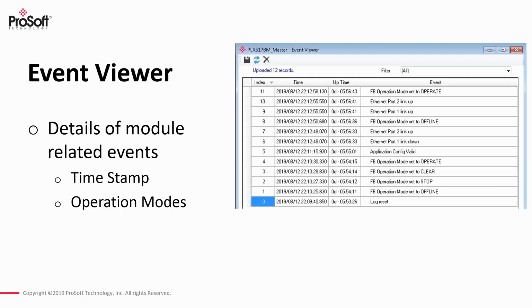And so say, for instance, you get an issue that occurs at 10 o'clock at night. When the maintenance crew comes in the next day, or they get things back up and running, somebody can go back through this event log, and it's going to tell you things like if the bus operation mode was set to offline, or if one of the Ethernet ports went down on the network. It's going to give some detailed diagnostic data, which will assist in troubleshooting any issues that may occur on the network.